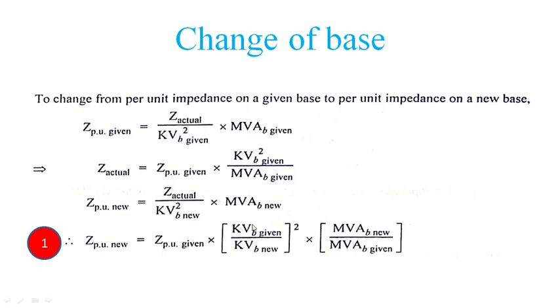Next, consider that we have some per unit impedance value for each equipment in the network, which is to be considered as a given value. The per unit impedance value specified in the network or equipment is the given per unit impedance value. So we want to find out the new per unit value for the change of base values. The new base values are denoted with subscript new. Subscript new is the new base value for MVA, and this is the new base value for kV.